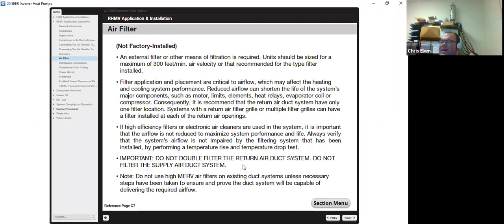Also, do not use very high MERV filters on existing duct systems unless necessary steps have been taken, which we'll get into a little later. They're super sensitive to static pressure. If your static pressure is excessive, over 1, especially when you start going into 1.2 and beyond, you're going to start having inverter faults. You'll also have airflow issues and additional faults as well. So airflow is very, very, very critical.